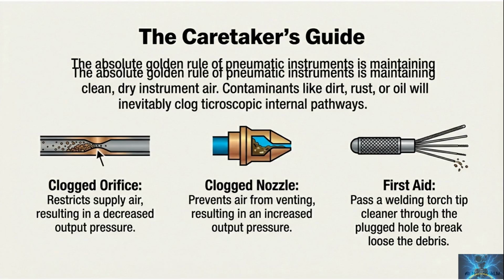The Caretaker's Guide. The golden rule of pneumatic instruments is simple: keep instrument air clean and dry. Dirt, rust, and oil can clog microscopic orifices and nozzles inside these devices. A clogged orifice restricts supply air and typically drives the output pressure lower than it should be. A clogged nozzle prevents proper venting and typically drives the output pressure higher than it should be. A practical first aid technique is gently passing a torch tip cleaner through the plugged hole to break loose debris. Always isolate and depressurize before cleaning, and be careful not to enlarge precision holes or you can permanently change calibration.